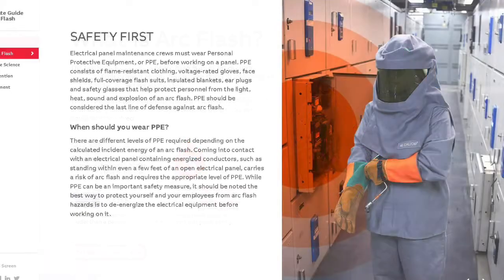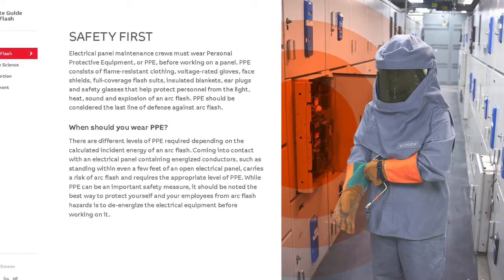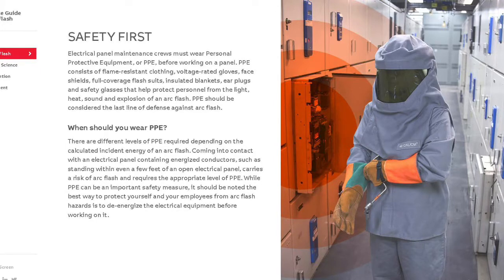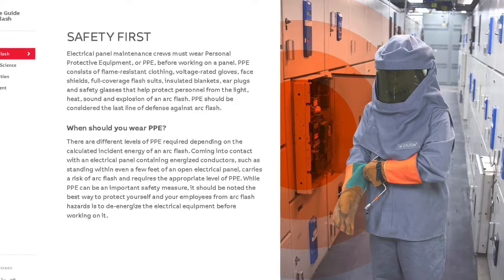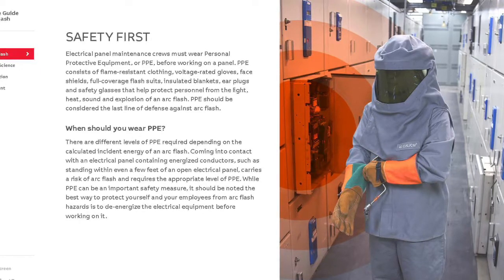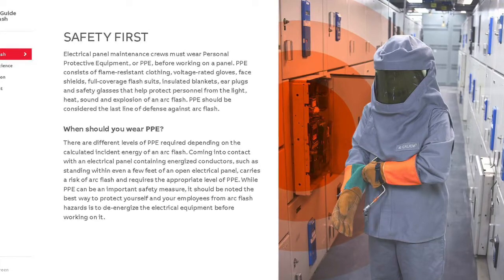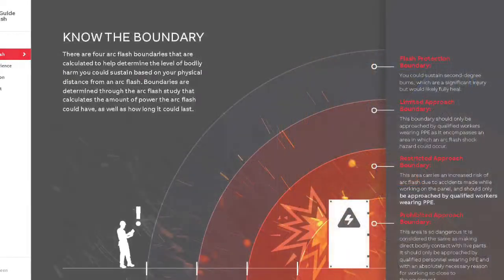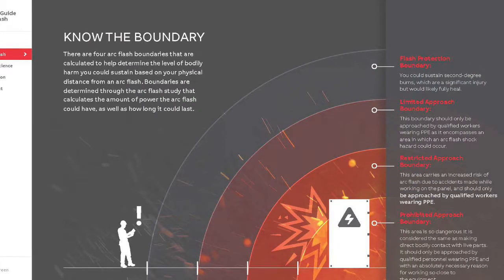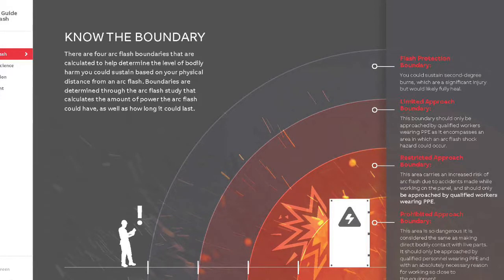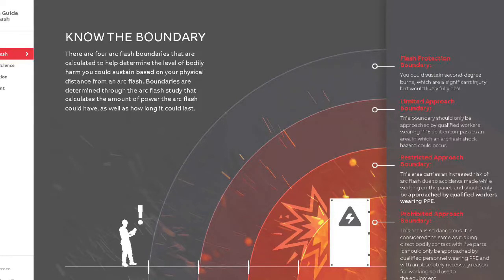There are different levels of PPE required depending on the calculated incident energy of an arc flash. While PPE can be an important safety measure, the best way to protect yourself from an arc flash hazard is to de-energize the electrical equipment before working on it. There are four arc flash boundaries calculated to help determine the level of bodily harm you could sustain based on your physical distance from an arc flash. Boundaries are determined through arc flash studies or using PPE category method tables.